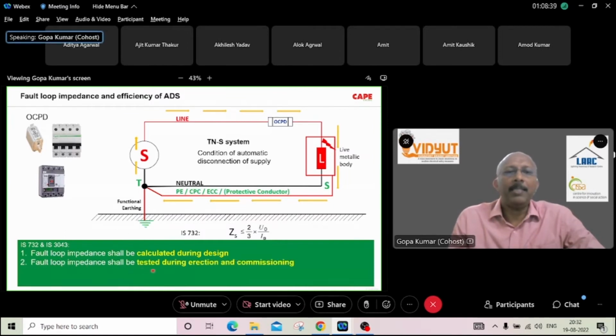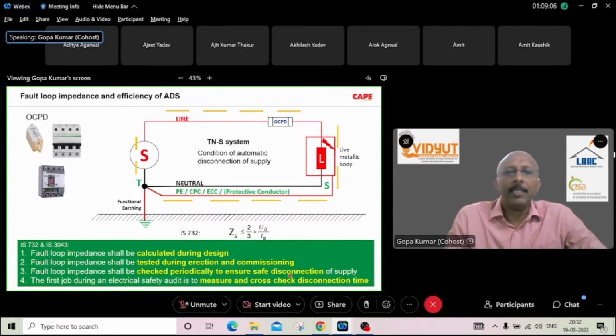Fault loop impedance shall be tested during erection and commissioning. Before you connect your equipment, you have provided an MCB, but whether the MCB will trip or not, you should test. Fault loop impedance shall be checked periodically to ensure safe disconnection of supply. Say, for example, every 2 years, every 3 years, or every 5 years, depending upon the criticality, we are supposed to do the periodic testing. And in every electrical safety audit, the first measure to be checked is this parameter called fault loop impedance, just to ensure that your protective devices are able to trip within the desired time.